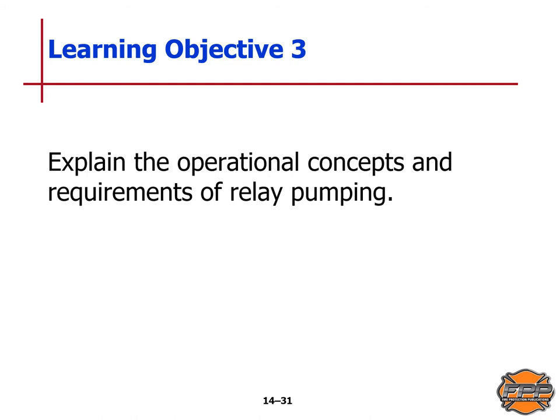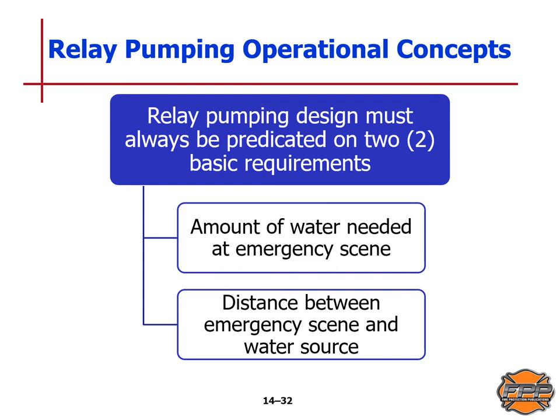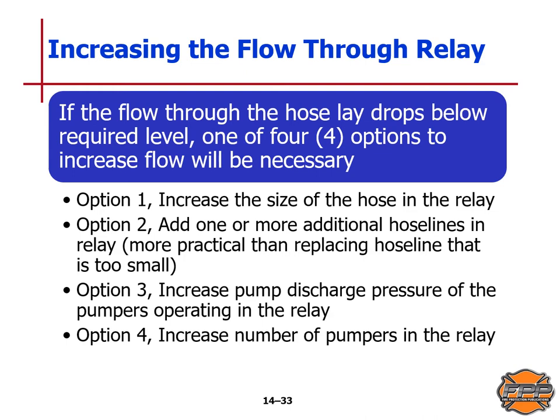Learning Objective 3: we will explain the operational concepts and requirements of relay pumping. Relay pumping design must always be predicated on two basic requirements — first, the amount of water needed at the emergency scene, and second, the distance between the emergency scene and the water source. If the flow through the hose lay drops below the required level, the flow will need to be increased. There are four options: one, increase the size of the hose in the relay; two, add one or more additional hose lines in the relay; three, increase pump discharge pressure of the pumpers operating in the relay; and four, increase the number of pumpers in the relay.